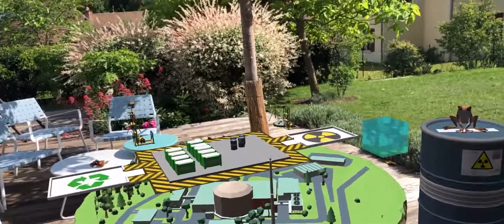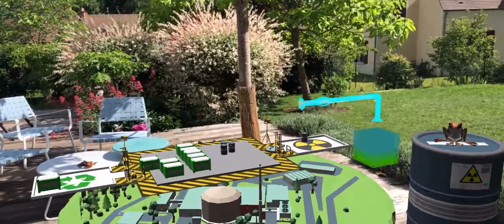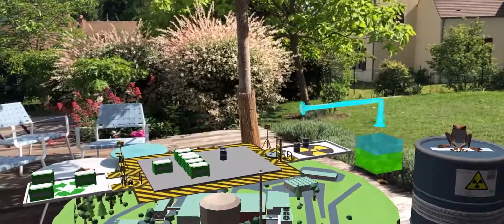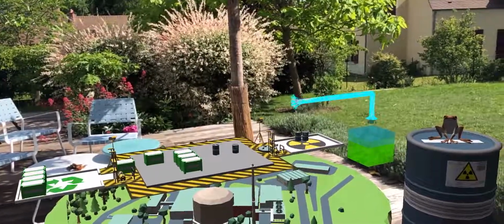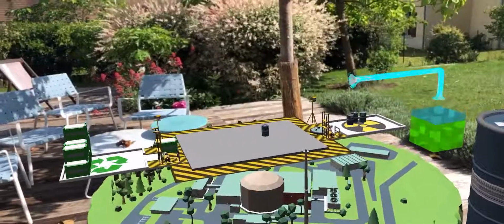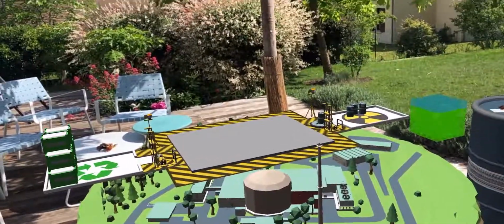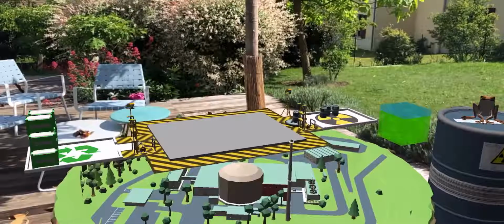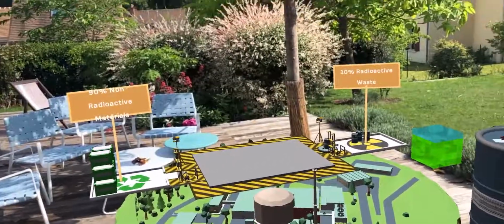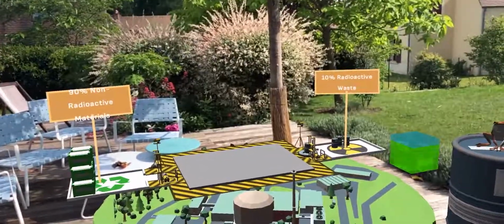When the reactor was operational, the contamination was already contained in hermetically sealed circuits. This is why most of the material in the nuclear facility is not contaminated. During the dismantling phase, besides paying attention to the homogeneous groups, there is another golden rule: the components must be removed in the order from the cleanest to the most contaminated. With this precaution, 90% of the material can be defined as clearable, uncontaminated. Waste traceability and its physical and radiological characterization are fundamental.